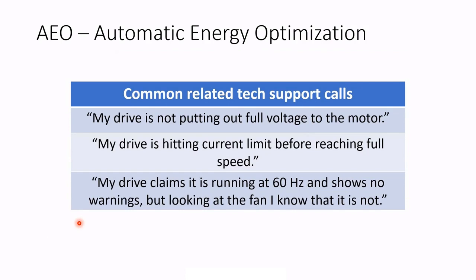Now, some common related tech support calls. Having been in tech support for many years, I would regularly get calls from someone doing an installation or troubleshooting who measures their motor voltage and calls to say there's a problem — the drive is not putting out full voltage to the motor. That is likely because the AEO function is active. I would guide them to parameter 103 to turn AEO off and set it to variable torque, and then their drive would be putting out full volts. Another common call during commissioning: the drive is hitting current limit before reaching full speed. Or, the drive claims to be running at 60 Hz with no warnings, but the fan visibly isn't going full speed — that's another consequence of AEO being too active, reducing voltage by too much so the motor is actually stalling.